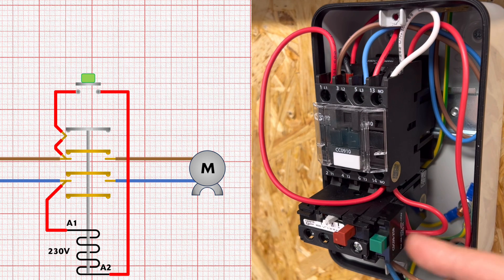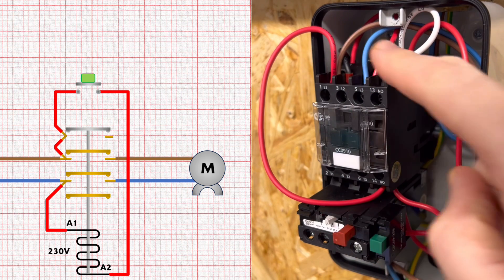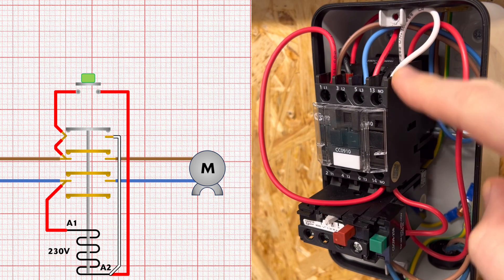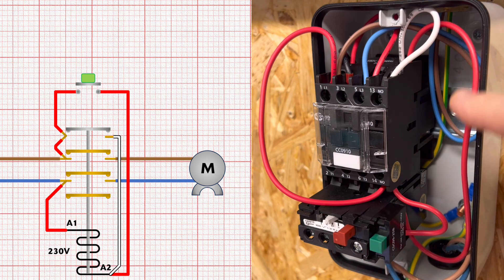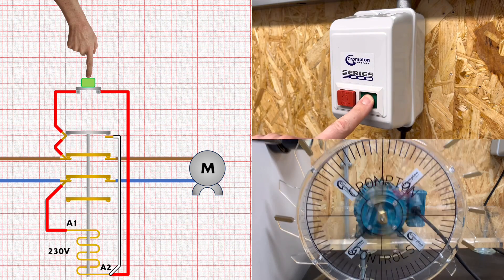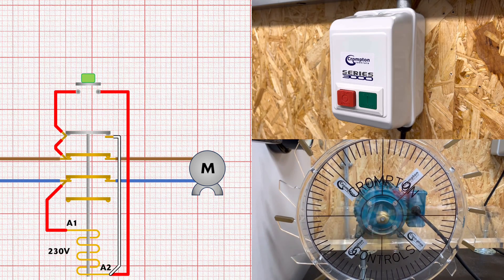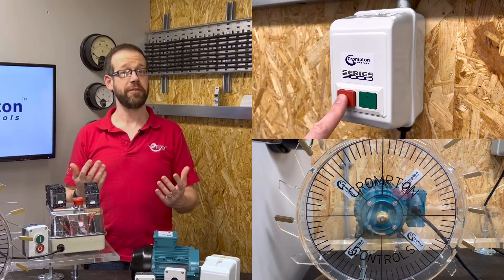We're going to use this auxiliary contact for a different purpose. If we wire through our start button as before, but also wire the control circuit through the auxiliary contact so that the auxiliary contact and the start button are wired in parallel with each other — now watch what happens when I press the start button. The motor starts as it did before, but when I take my finger off the start button the motor continues to run. That's because the coil is holding the auxiliary contact in, which means the coil is now connected to the supply even when the start button isn't pressed. Clever stuff!